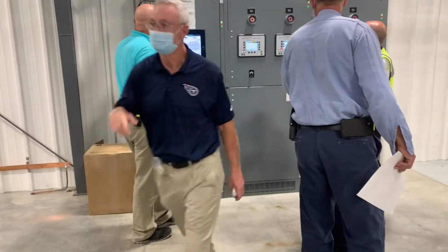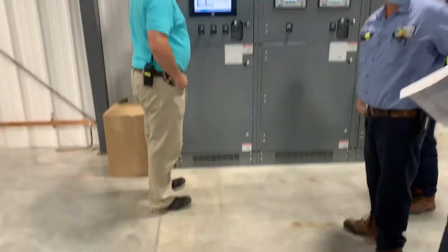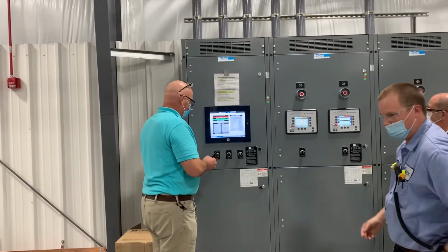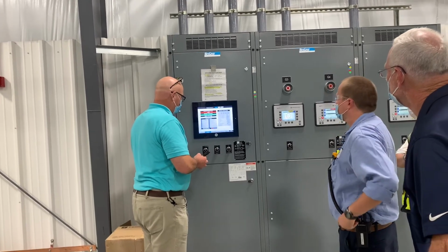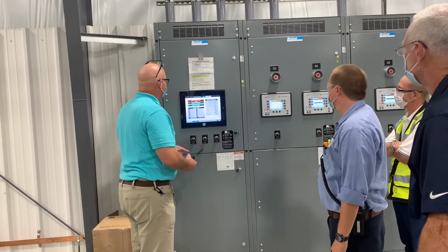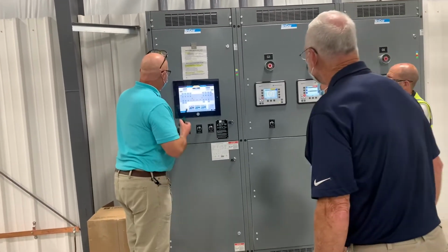What is the risk of an arc flash? Have we utilized the table within NFPA 70E identifying the likelihood of an arc flash to occur? What is the arc flash boundary? Is confined space involved? Is there excavation or trenches involved? What about slips, trips, and falls? Are you dealing with any hazardous materials like batteries?